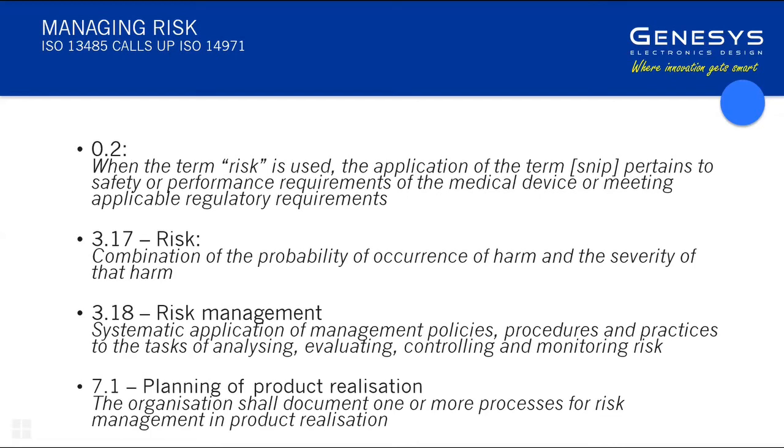One I'd like to emphasise is the definition of risk. And risk is used as a broad term. You can consider commercial risk and technical risk and timescale risk and all sorts of other risks. But in considering within the context of ISO 14971, it's important to apply it within the scope of that definition. So it pertains to safety or performance of the device, so risk of causing harm or injury to the patient, the user, or the environment. So it's very important to constrain consideration of risk to that definition.